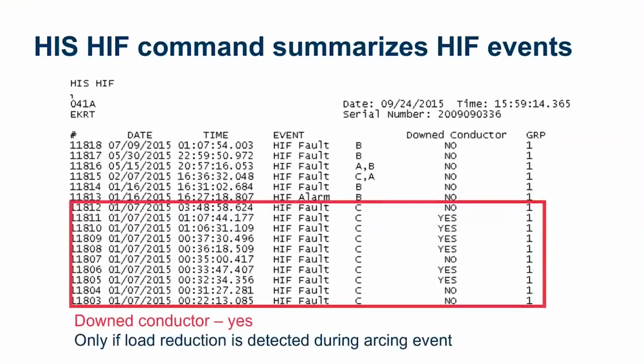So similar to the HIS command, in any SEL relay, if you issue the history command or the HIS command, it gives you a list or a history of all the event records. That's the similar case with high impedance fault detection events. So if you issue the command HIS space HIF, you're going to get a history of all the high impedance fault events. So you can see that it gives you information of what the event number is, what the date is, what the time of the event is, and then it tells you what type of event it is. Is it a HIF fault or is it a HIF alarm? It also tells you which phases were involved in the fault. So you can see that more than one phase can also be involved in a specific fault. It also tells you which group was active at the time of the fault, and it also tells you if it was a downed conductor or not.